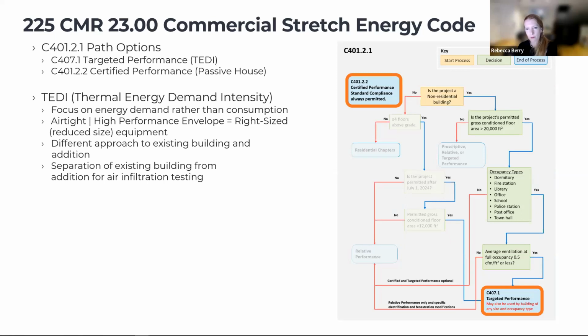So you make improvements where you can to the existing building, you build the addition to the building completely with this airtight, super high performing envelope, and you understand that these two are going to perform differently. So when you do testing, you do it separately. But the great thing is, because you have really driven this energy demand way down, you're going to get a really high performing building out of the project. You're going to hit very low EUIs and put yourself in a position to potentially reach zero net energy.